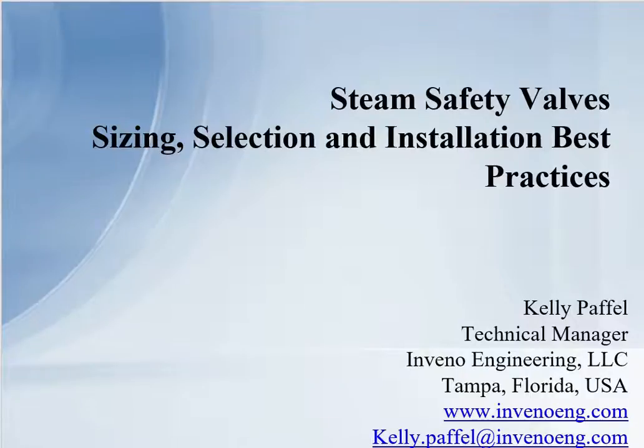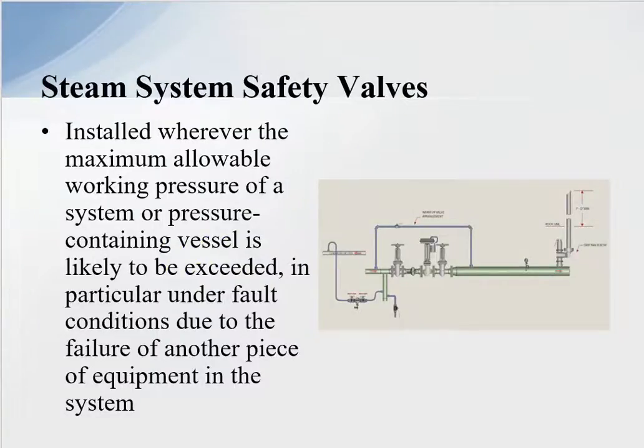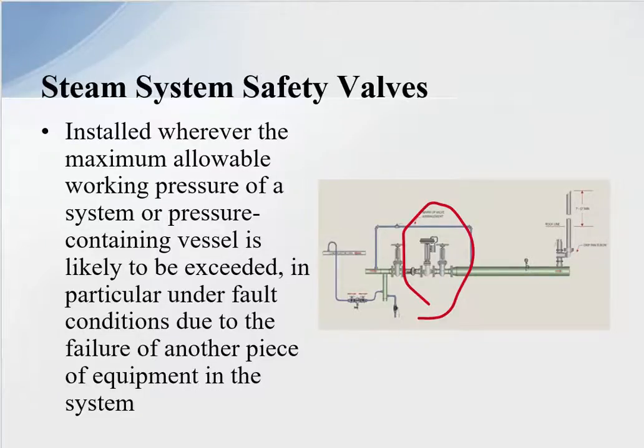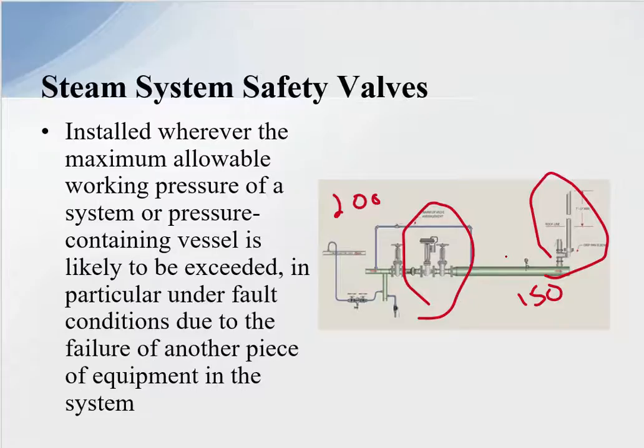Today I want to talk about steam safety valves: sizing, selection, installation, and best practices. Steam safety valves are installed wherever the maximum allowable working steam pressure of a system, or pressure-containing vessel, is likely to be exceeded — in particular under fault conditions due to the failure of another piece of equipment in the system. In a typical system, if we have a pressure reducing valve with 200 PSI upstream and our equipment downstream is only rated for 150 PSI, we need to protect it with a safety relief valve. That safety relief valve will typically be set for the lowest rated equipment or component in the system by pressure and temperature rating.